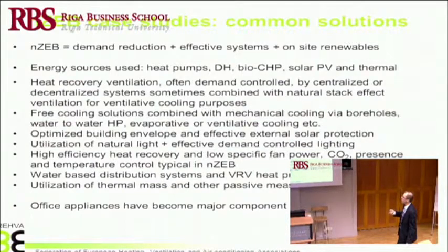Optimized building envelope, in all cases, in both climates, although the solutions are different. Utilization of natural light, yes, no other way to reduce electric lighting demand. High efficiency heat recovery and low specific fan power are needed in all climates. And then you indeed can use demand controlled solutions. Especially in cold climate, you need a water-based distribution system for the heating, because a circulation pump uses much less electricity compared to all-air systems, where you will need a significant contribution of fan energy if you try to use air heating. And it seems to be the same for the cooling and for the heating.